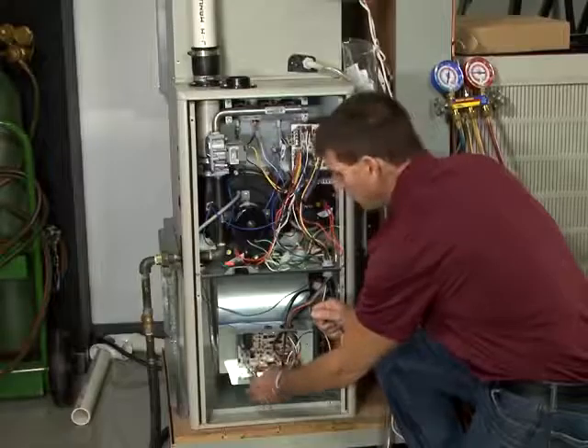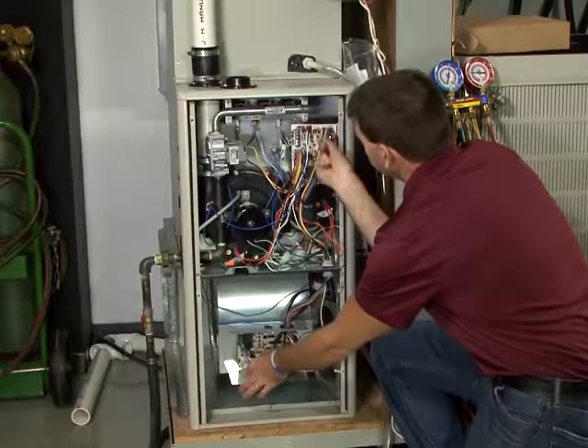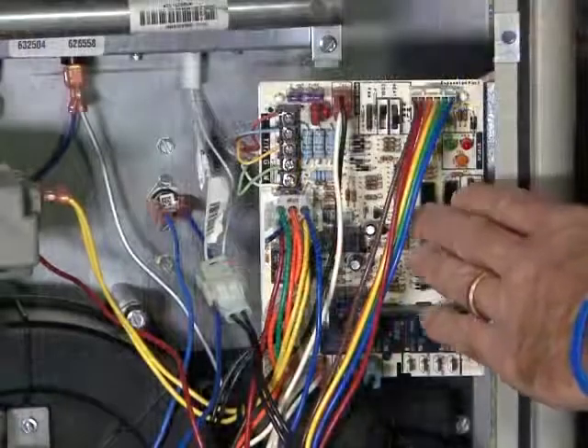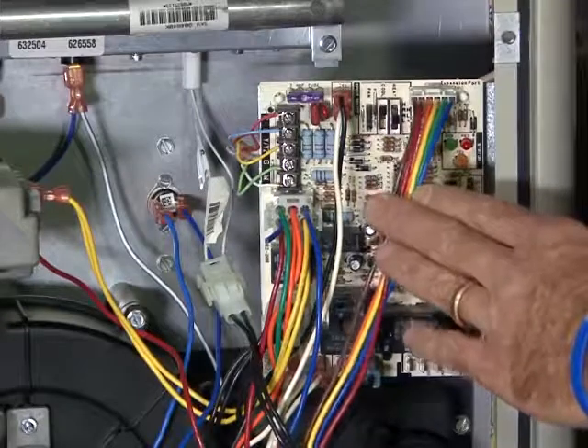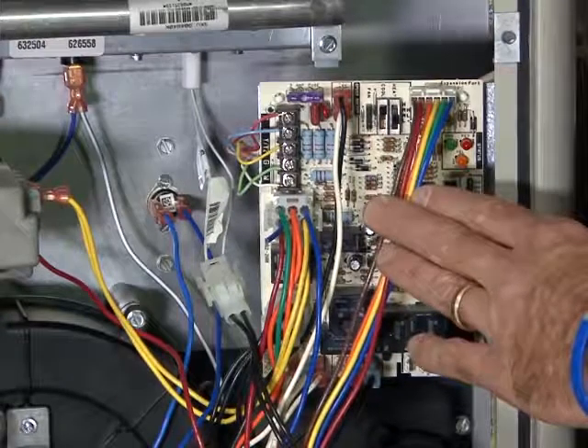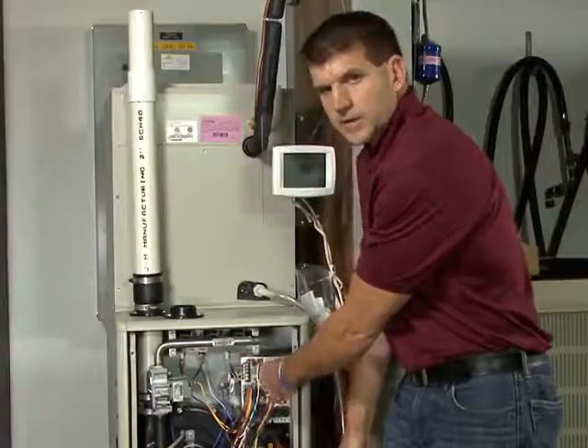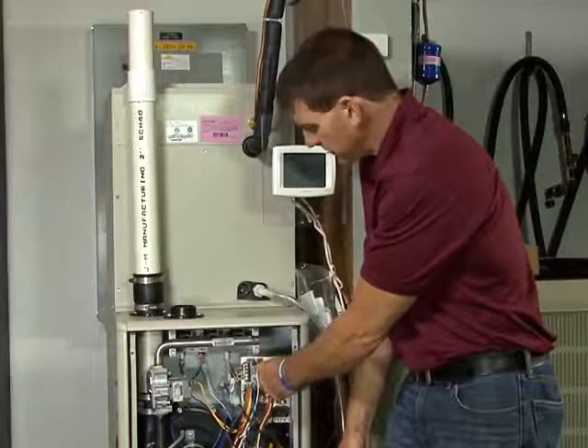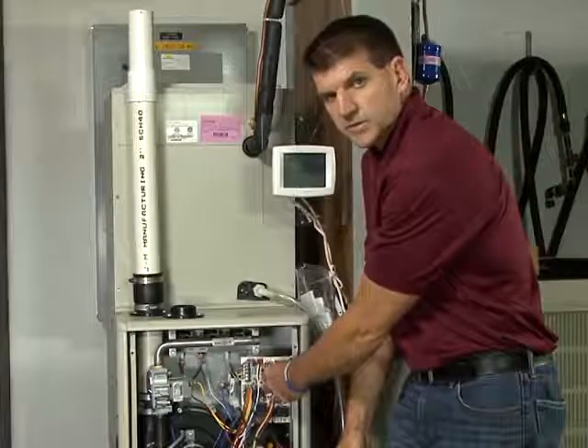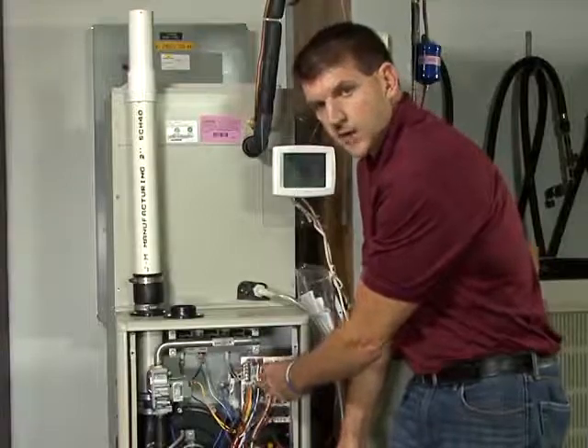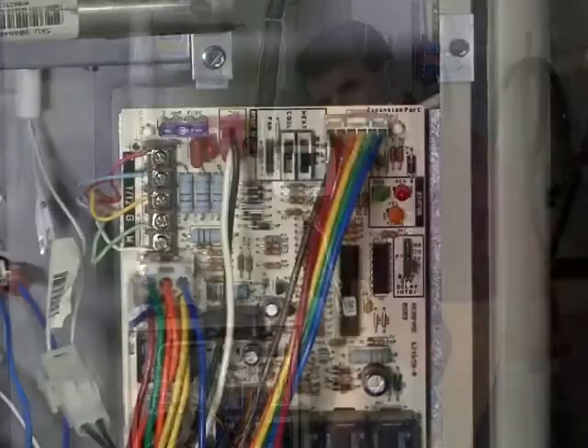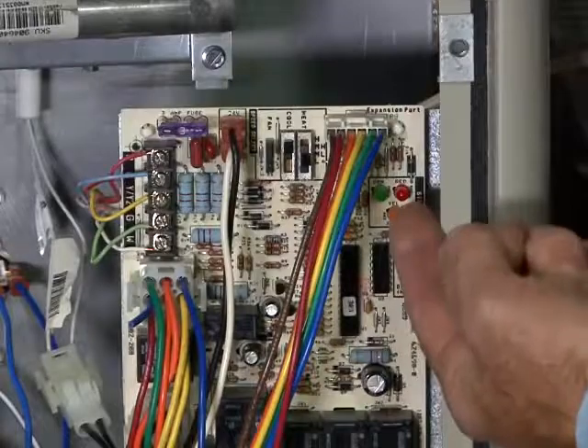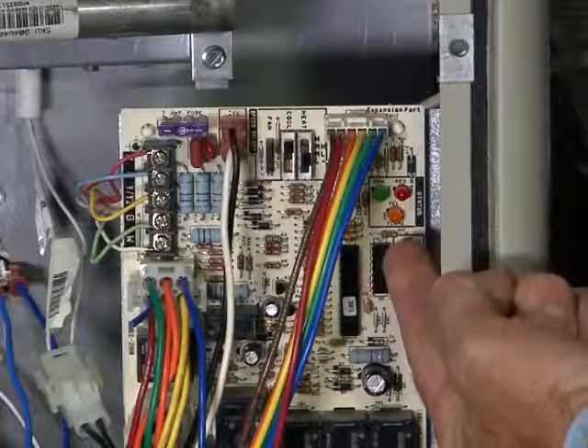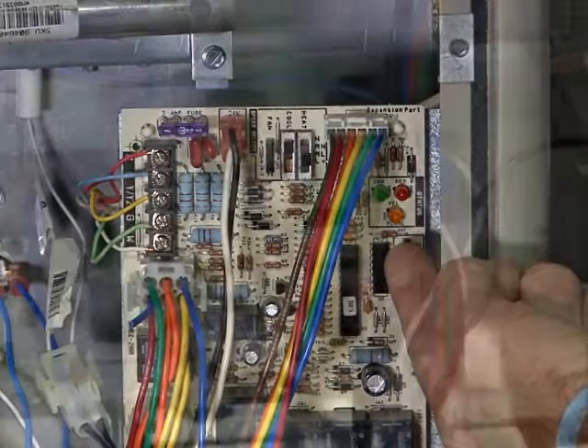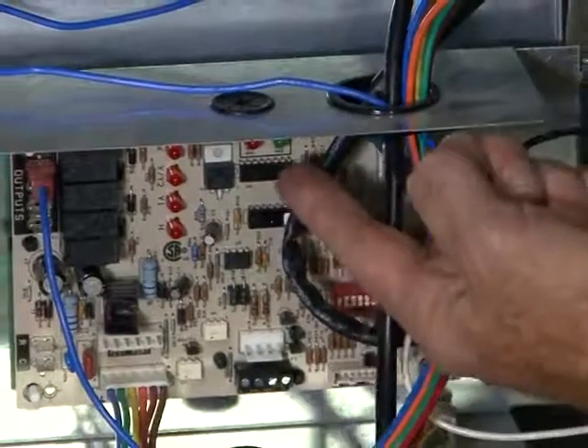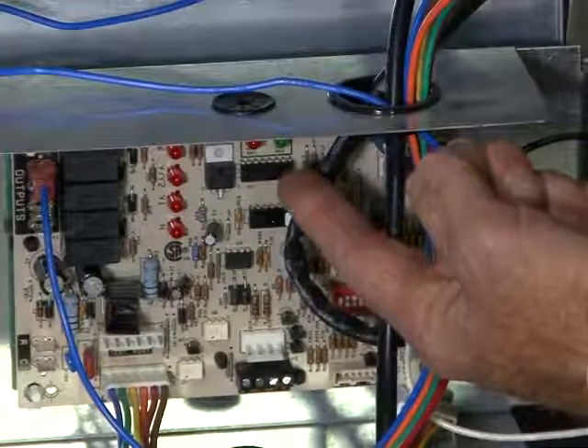You can also ohm from plug to plug, and you can ohm from wire to wire to make sure that we don't have a shorted circuit. If your connections are good, and you don't have any shorted wires, and you're getting a communications fault, then I would advise to just go ahead and replace the motor control board. If you're getting a motor fault code indicated on the main control board and at the motor control board, this indicates a problem is most likely in the motor.